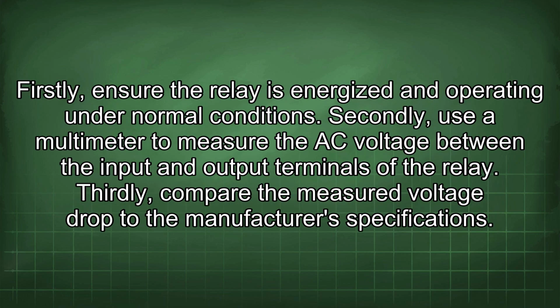Firstly, ensure the relay is energized and operating under normal conditions. Secondly, use a multimeter to measure the AC voltage between the input and output terminals of the relay. Thirdly, compare the measured voltage drop to the manufacturer's specifications.